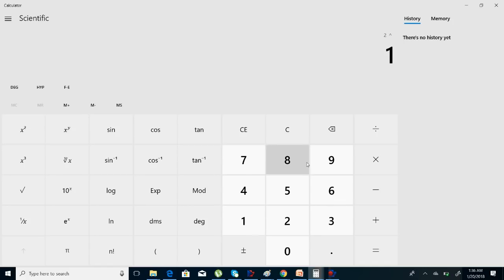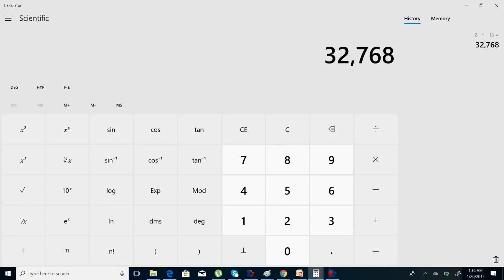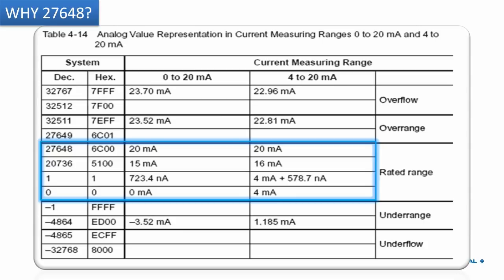Now, 2 raised to 15 is 32768 — but that is not the value we were getting. We were getting 27648. Why? Because 27648 is approximately 85 percent of the total 16-bit value of 32768. So we are only using 85 percent of the whole value range.